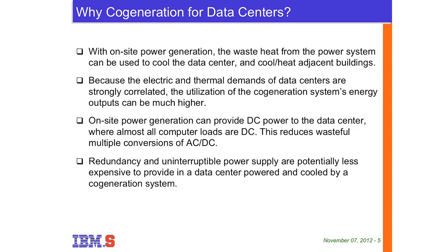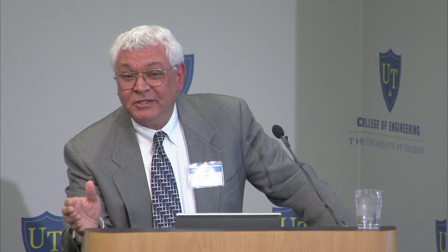So why cogeneration for data centers? With the on-site generation of power, the waste heat from the power plant could be used for useful things, such as producing cooling in an absorption chiller or producing heating—not because the data center needs heat, they have enough heat by themselves, but to heat an adjacent building.